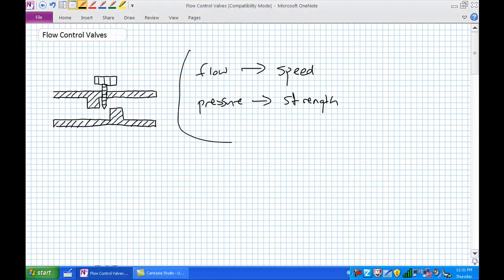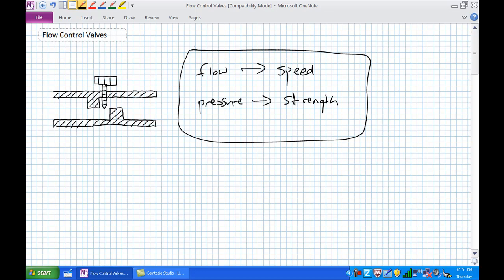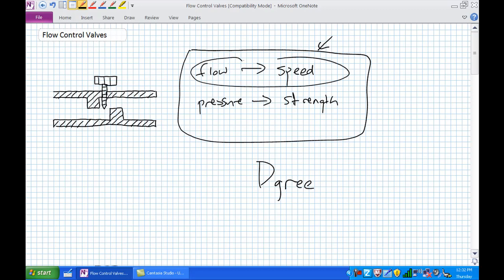The general concept is this: flow is directly proportional to speed, and pressure is directly proportional to strength. This is one of the most important concepts you can understand for a hydraulic system. If we increase the flow into an actuator, we'll increase its speed. If we increase the pressure available to it, we increase the strength available to it — it can lift a greater object.